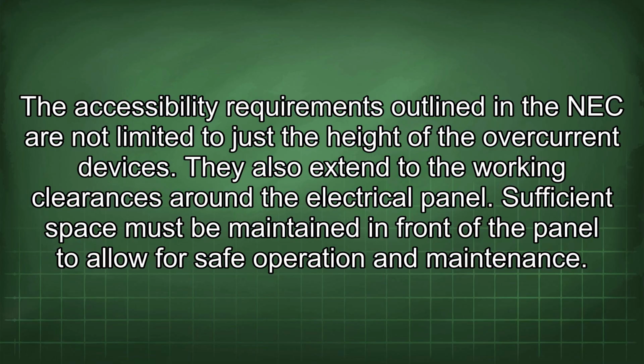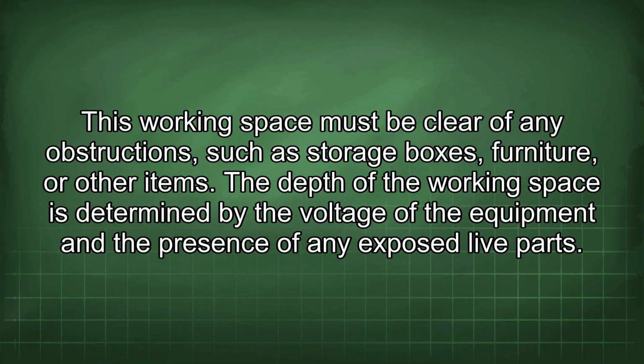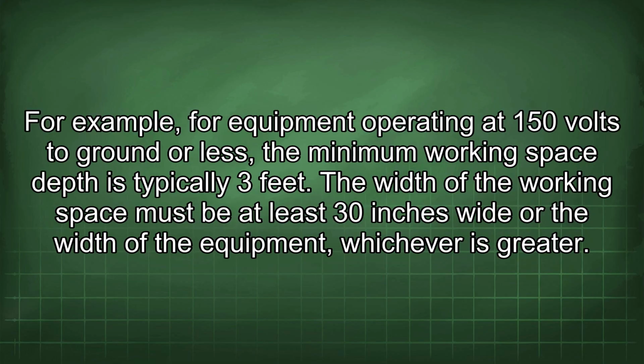Sufficient space must be maintained in front of the panel to allow for safe operation and maintenance. This working space must be clear of any obstructions, such as storage boxes, furniture, or other items. The depth of the working space is determined by the voltage of the equipment and the presence of any exposed live parts. For example, for equipment operating at 150 volts to ground or less, the minimum working space depth is typically 3 feet.